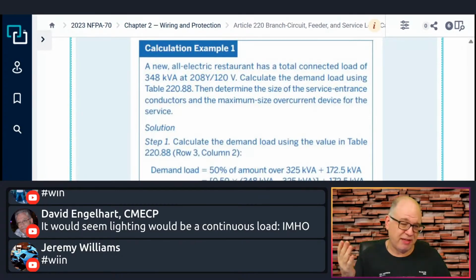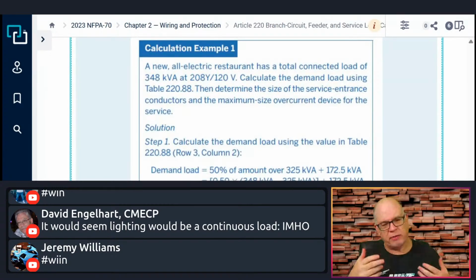Another example is EV charging. We size those branch circuits to 125%, but when we do the load calculation, we take the wattage, 7,200 minimum, or the nameplate value, whatever it is. We don't apply the continuous load factor on the service load calculation. So along those same lines, it's already figured in with the optional method and the diversity involved.